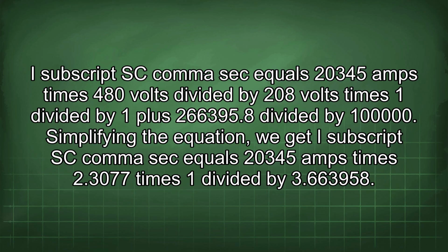I_SC,sec equals 20,345 amps times 480 volts divided by 208 volts times 1 divided by 1 plus 266,395.8 divided by 100,000.